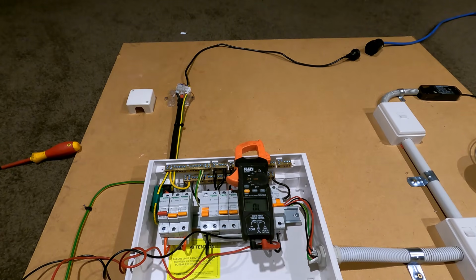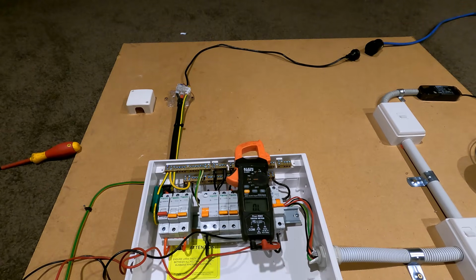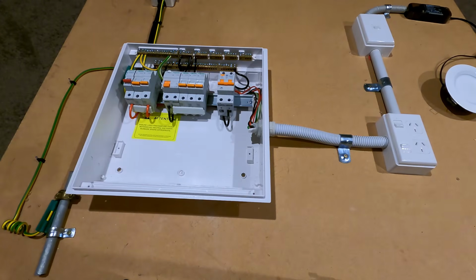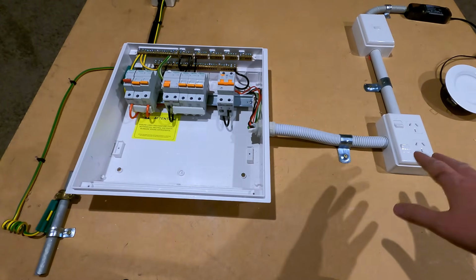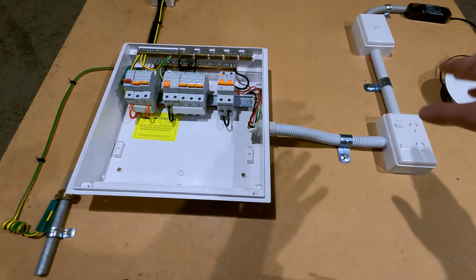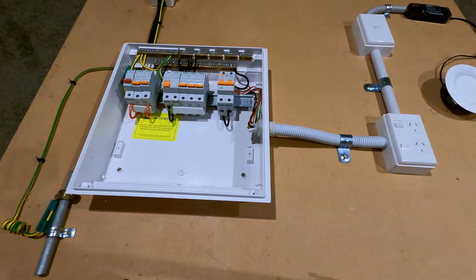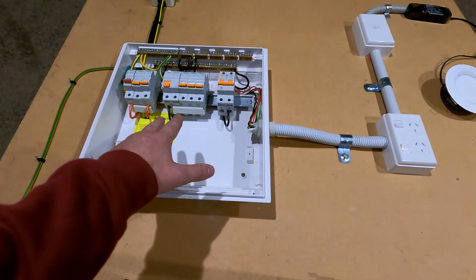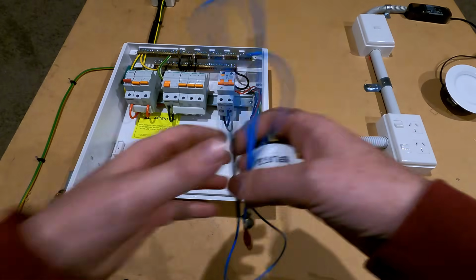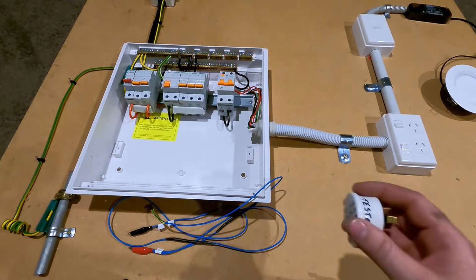The next one we'd run through is a sub-main polarity. There's no sub-mains running off this board, so we can skip that one on here. If you do have sub-mains, make sure you go through and verify that the polarity of those cables are correct. Sweet. So the last part of polarity testing is getting the load side of the circuits tested to make sure that the polarities are fine at your lights, at your sockets, and at your appliances that you've got running off the circuit breakers. What I've got are two tools for polarity testing. These ones I made myself.